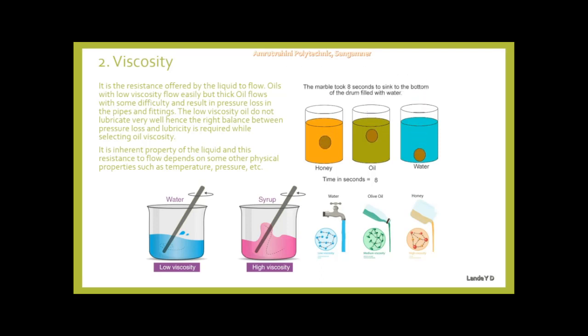more quickly. In hydraulic systems, viscosity is important for several reasons. First, it affects the efficiency of the system by influencing the pressure drop across the system and the energy required to move the fluid. Second, it affects the ability of the oil to lubricate moving parts and protect against wear and damage.